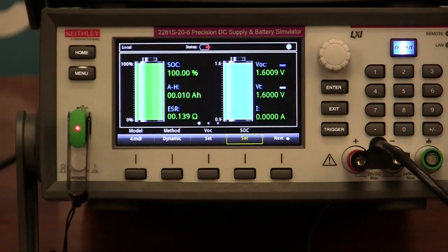So now that you have the model loaded into the 2281S, you can use that model to test your device. So now with the model loaded into the 2281, you can efficiently and repeatably test at any state of the device.